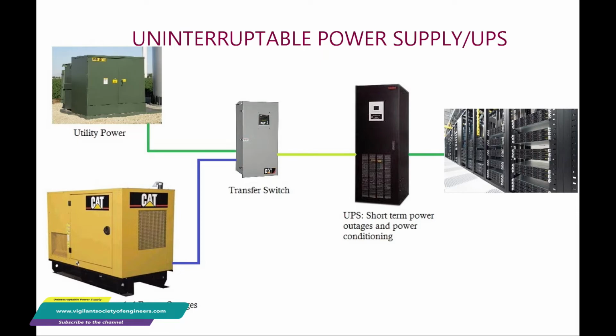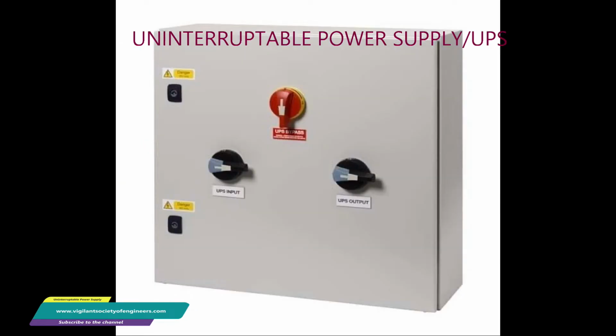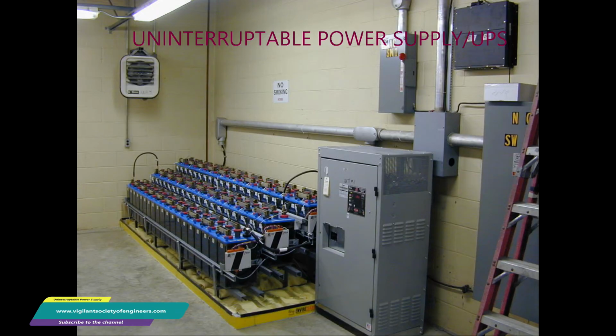Now, the external maintenance UPS bypass, also called a wall mount or wraparound bypass. The external maintenance bypass allows the UPS to be removed or replaced without interruption to the load, and if the actual maintenance bypass is fed from the supply, it will allow UPS load testing. It is typically engaged during a repair, or when checking the autonomy under simulated load conditions, to see how long you have available usage and ensure the site load is supported.